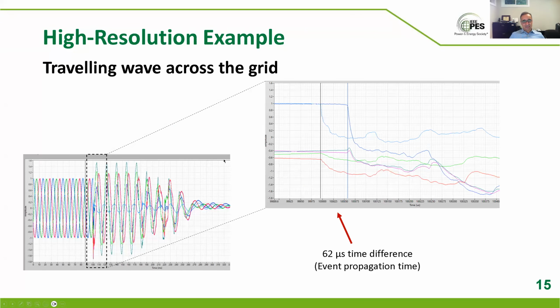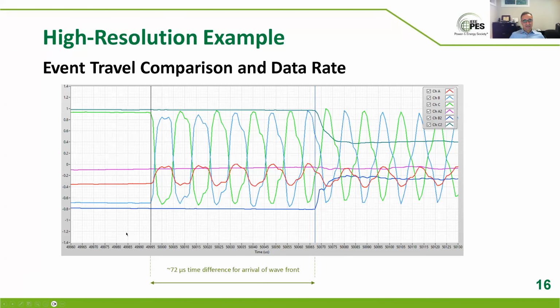And this is another one. I sort of zoom in. This is similar, actually the same waveform I showed earlier, about losing information. You can see that there's a 72 microsecond time difference between arriving at one end versus the other one. Let's say it's the same line with 80 microsecond total line length. With the 72 microsecond time difference, going from the light green to the dark green transitions, that says it's 4 microseconds from one end and 76 microseconds from the other end. And 4 microseconds times 300 meters is about 1.2 kilometers.